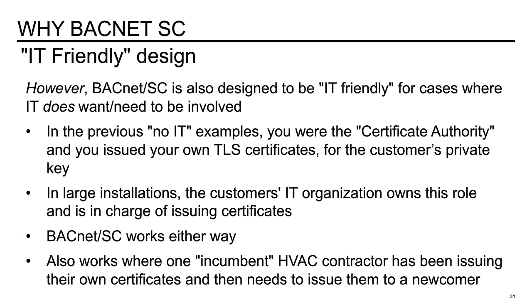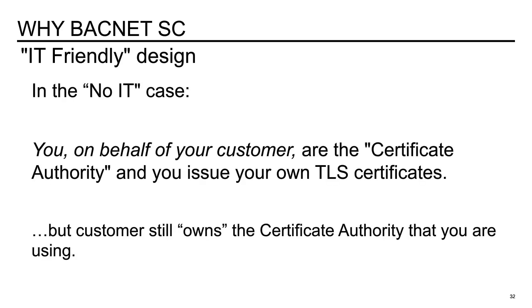This is really important. The certificate authority must be owned and managed by the customer, not the BAS contractor or whatever other system you have installed that uses BACnet SC. You as a customer need to make sure that you own that certificate authority. In the addendum, YY 7.4.1.2 requires the signing certificate authority shall be controlled by the site, aka the customer. So you, on behalf of your customer, as an installing contractor, issue your own TLS certificate, but the customer still owns the certificate authority that you're using. It belongs to the customer.